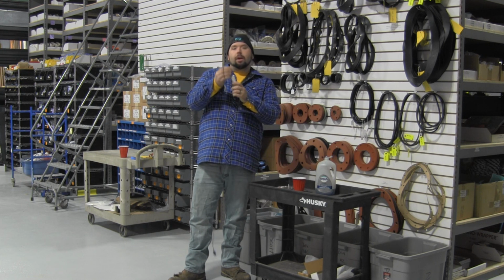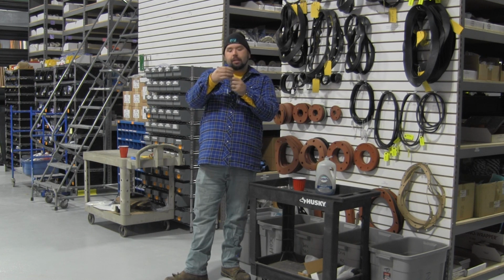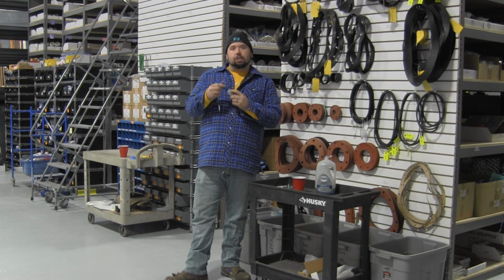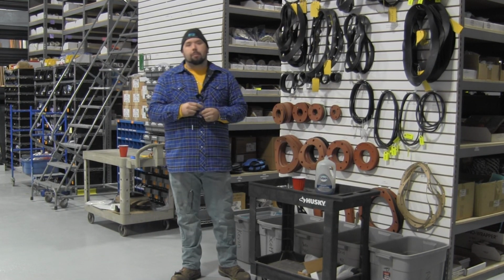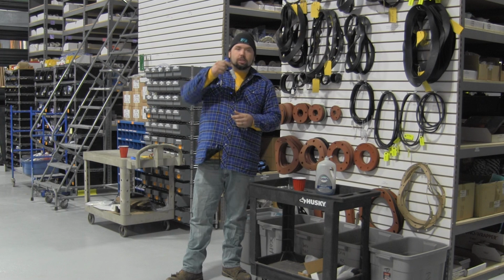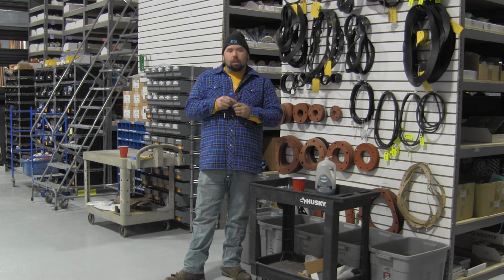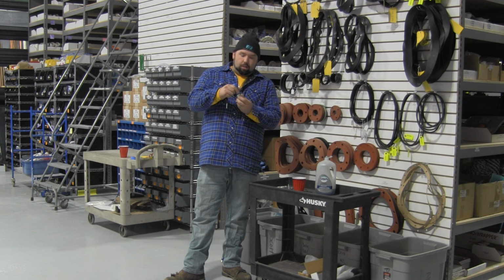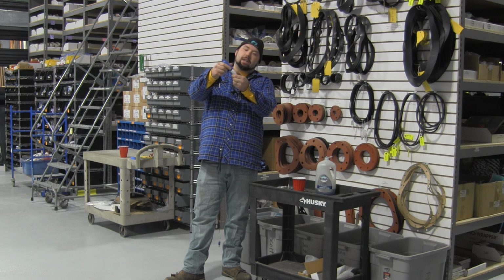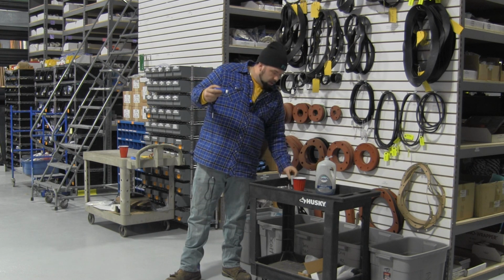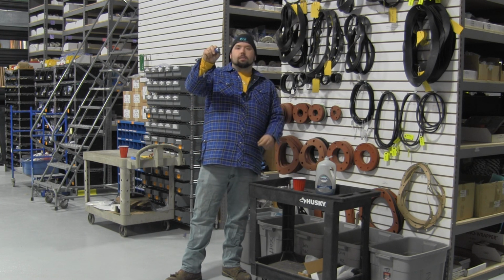You're going to unthread the probe. Be careful that you don't bend the tip of the probe because you can fracture the eye of the probe, and at that point you'll need a new probe. So once the probe is out of the flow cell, I'll unscrew the cap just to kind of show you. You're going to have the eye of the probe right there.